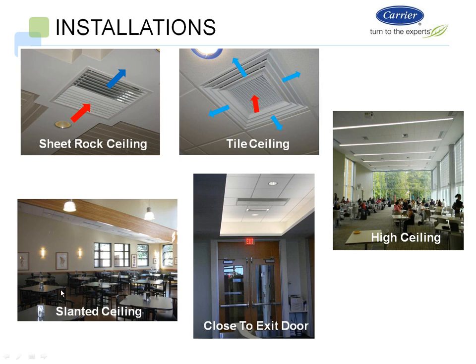If you look at the slanted ceiling off to the left, these actually have the ability to, they're collared inside. So you know, it isn't all this water running all the way down to the end of the room and out the window there. Those coils are perfectly level and straight inside that soffit there. And then you have a collar on the unit so that you can handle any type of sloped ceiling. It's standard 3 to 3.5 inch, and we can make those custom if your pitches were any different than that.